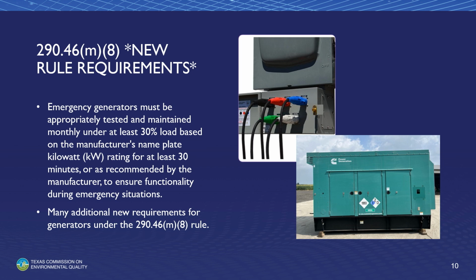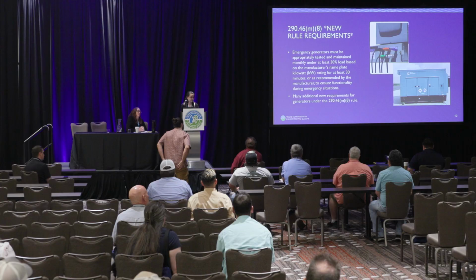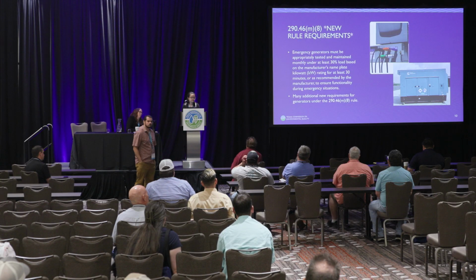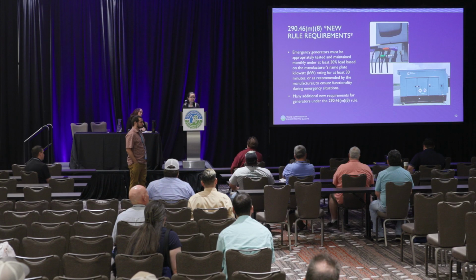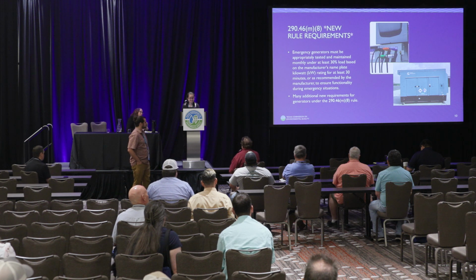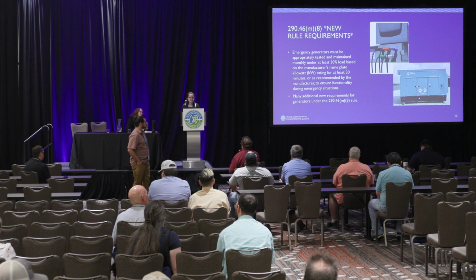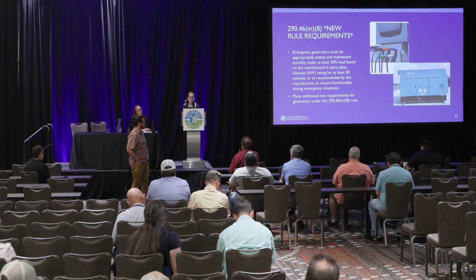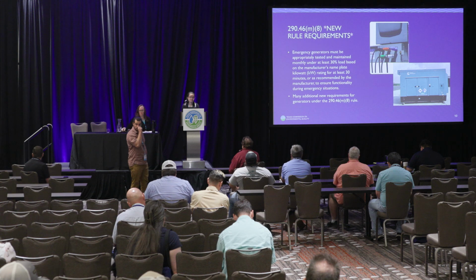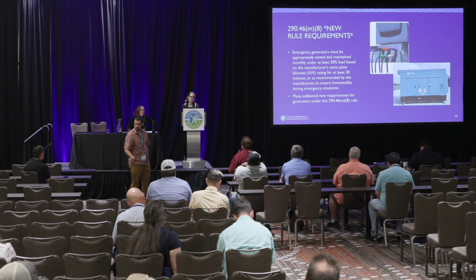Yeah, I just wanted to say that I've seen a presentation about generators, and one of the issues they found is that sometimes if you use diesel, you have to check the longevity of that and make sure it hasn't deteriorated. And so you must follow the maintenance and operating procedures for the generators. Make sure you follow the manufacturer requirements, because your fuel could be too old and not useful, and it can cause deterioration and degradation of the fuel whenever you get ready to use it in an emergency.